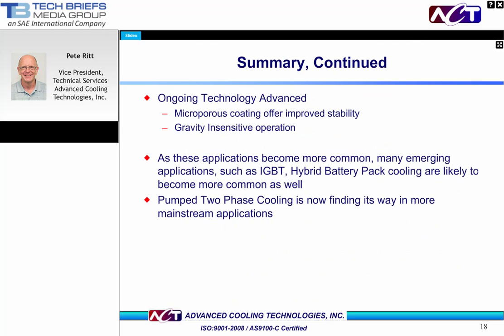Continuing, in addition, some new technology enhancements were demonstrated. Microporous coatings on the mini-channel heat sinks were shown to improve system stability and temperature uniformity by increasing the number of nucleation sites across the evaporator surface. It was also shown that properly designed pumped two-phase cooling systems can handle multiple evaporators, even when the orientation with respect to gravity of the evaporators is different.